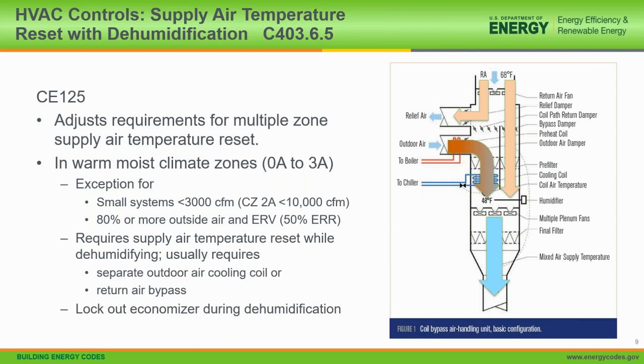So this should provide significant savings. There are some size limits based on cost effectiveness. So if your main unit fan is below 3,000 CFM in those climate zones, or below 10,000 in 2A specifically, it didn't show to be cost effective there, so those would have an exception. And also, if you're dealing with a DOAS unit, that dedicated outdoor air, that is basically 100% or 80% more of outside air, then you would not be required to do this either, since you don't have the opportunity to mix with the return air.